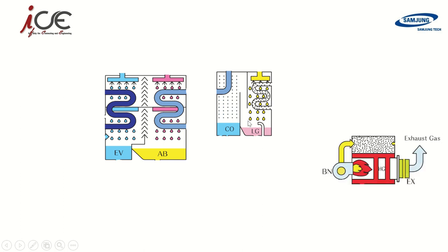The third shell is the high temperature generator, which consists of a bundle of iron pipes made of carbon steel, fixed vertically. The solution passes inside the pipes and the hot gases pass around them from outside. The heating of lithium bromide occurs inside it, indicated in red color, and the vapor is separated from lithium bromide by heating. Direct fire heats the lithium bromide using natural gas or diesel oil.